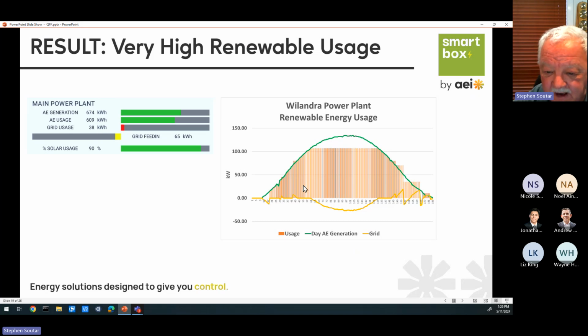So you can really see here, and if you actually look at it, you can see here where the bore pump started. It got up to here. Then this is a pivot power usage through here. The bore pump starts again. That's the pivot through here. And then the bore pump starts again and uses up to here. So this is two pivots. You can see one there and one here. And then the bore pump running on the top. That's as high as it is practically possible to use. So that was powered by 94% solar and 6% grid.